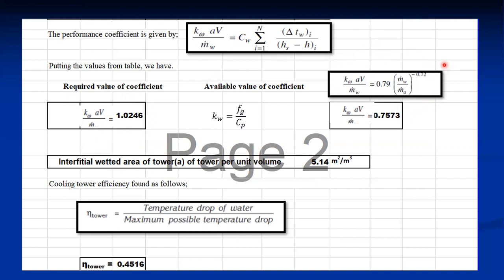The available value is calculated using the correlation given in the book or obtained experimentally during testing of the cooling tower after manufacturing. From this correlation, we get the available (experimental) value. Comparing: the experimental value is less than the demand value, which means the cooling tower is not performing at the expected capacity and needs improvement.